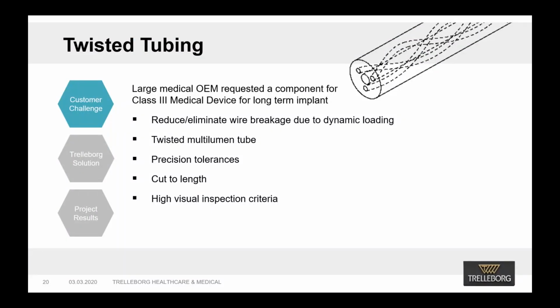The OEM approached Trelleborg to help manufacture a twisted tube expected to mitigate device failure due to repeated strain from bend loading, where the cable lead assembly met their electronic housing. The challenges of twisted extrusion processing are in controlling the twist angle and the stability of numerous dimensions to tight tolerances. This could involve 5 or 6 lumen, all with very precise tolerance in an asymmetrical cross-section, so imagine all of those walls and diameters with very tight tolerances.